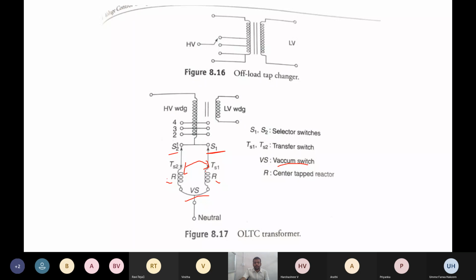So now when doing tap changing, while going from one position to another position, at that time you can witness some high spikes or some low spikes. So in order to protect our circuit, circuit means our transformer. Okay. So in order to protect our transformer, we are using vacuum switches. So these vacuum switches will act like our circuit breakers, just like a fuse, which breaks or makes any contacts. So in the fuses, it only breaks, not makes, but this circuit breaker can make and break. So that's the thing.